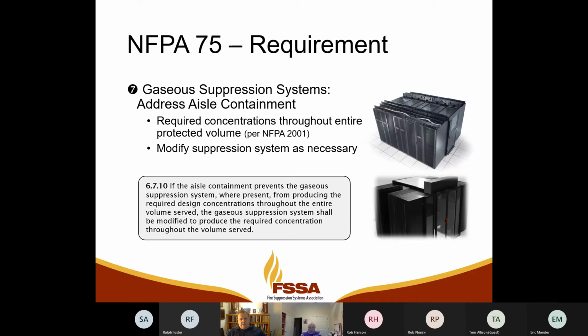On gaseous systems, the code says that you should build required concentrations throughout the protected volume and modify the suppression system as necessary. So if I'm coming back in and adding this cold aisle containment system, I need to build concentration throughout the entire protected volume. This is a new volume inside the room, and I need to make sure that I build concentration in it.